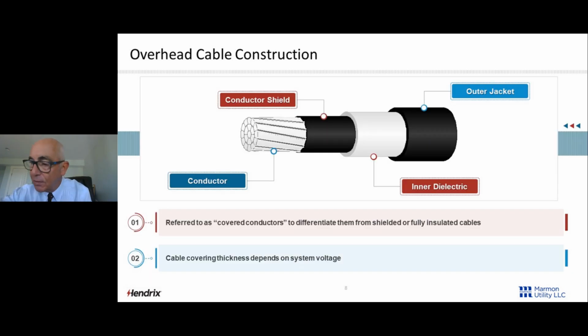And the conductor insulation system has 3 layers. The first layer is a conductor shield. That's basically going to smooth out the electric fields when we're in contact with a ground object. It's going to minimize the partial discharge. It's going to give us a higher BIL, and it's going to give us a longer useful service life.